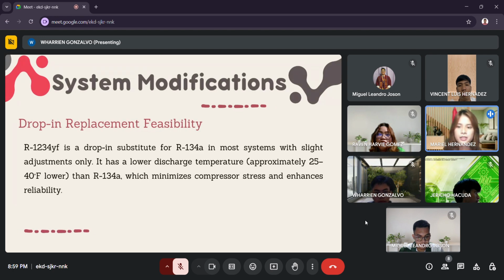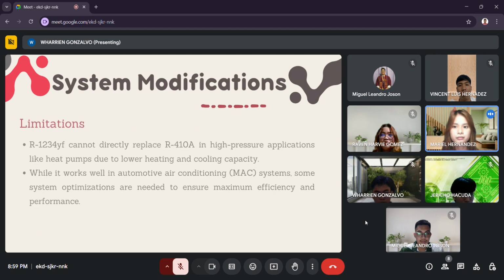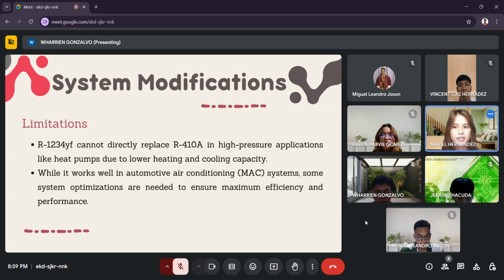In drop-in replacement feasibility, R1234yf is a drop-in substitute for R134a in most systems with only slight adjustment. It has a lower discharge temperature, approximately 25 to 40 degrees Fahrenheit lower than R134a, which minimizes compressor stress and enhances reliability. And it also has limitations. R1234yf cannot directly replace R410A in high-pressure applications like heat pumps due to lower heating and cooling capacity. While it works well in automotive air conditioning, or MAC systems, some system optimizations are needed to ensure maximum efficiency and performance.